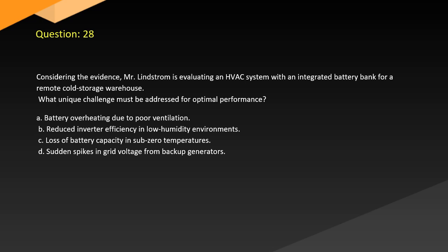Question 28. Considering the evidence, Mr. Lindstrom is evaluating an HVAC system with an integrated battery bank for a remote cold storage warehouse. What unique challenge must be addressed for optimal performance? A. Battery overheating due to poor ventilation. B. Reduced inverter efficiency in low humidity environments. C. Loss of battery capacity in sub-zero temperatures. D. Sudden spikes in grid voltage from backup generators.